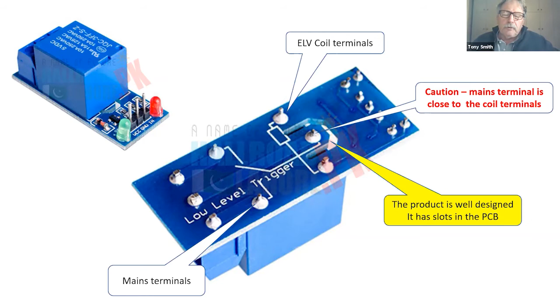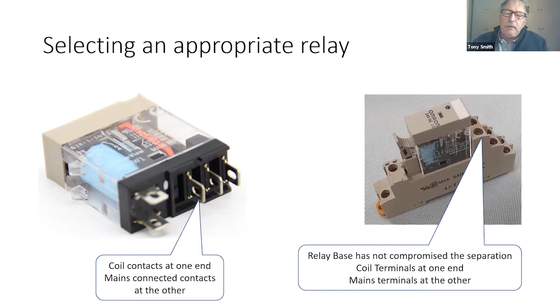Appropriate relays: in this one you can see the contacts are on one side and the coils on the other. Don't get trapped with the relay base you plug it into. You can see here the coil contacts on the left-hand side are on one side of the base, and the contacts are on the other. There are a lot of relay bases around where they mix them all together, and you can't get separation of the wiring.